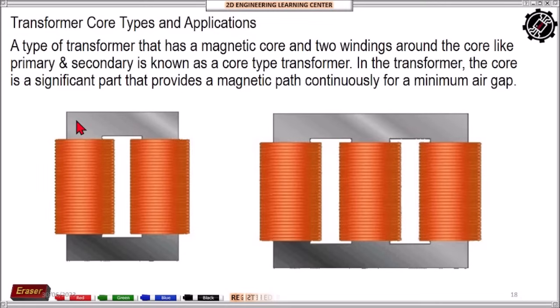Depending on the type of the core, the level or value of our iron loss also differs. So for these three types of transformer according to their core construction, the core type has the lowest. And also, because it has an overlapping joint with an additional pair of lamination, we also get a bit of condensed flux leakage.